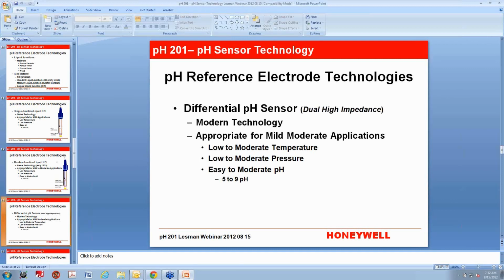It is a better technology than using a pH sensor that has a liquid fill inside if you're in a process situation. The downside is that they're expensive because they have two full-on pH measuring electrodes in them, and they will only work with an instrument that's designed to function with a dual high impedance or a differential pH sensor. They're appropriate for mild to moderate applications, low to moderate temperatures and pressures, what I would call easy to moderate pH, which is between 5 and 9 as well. Again, there's always exceptions on those numbers.